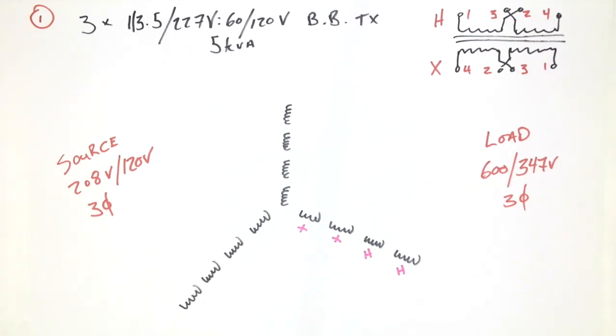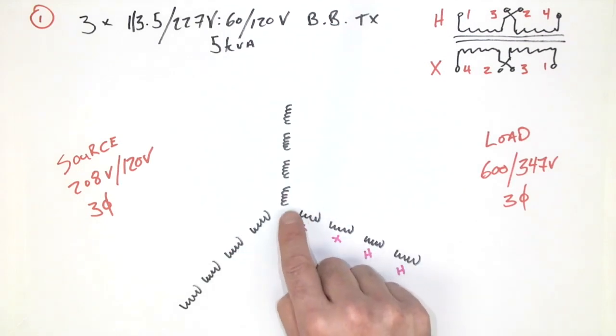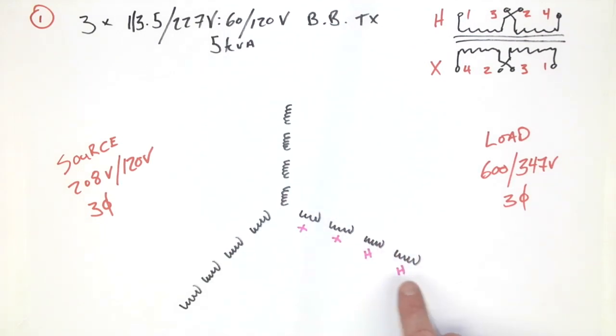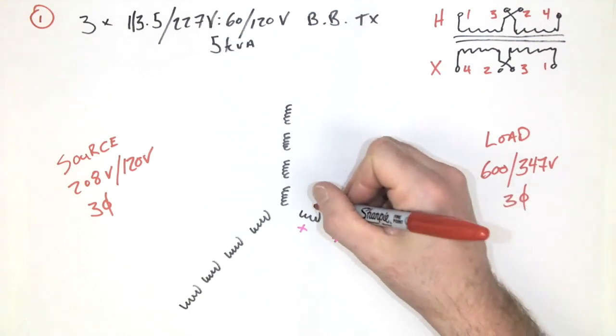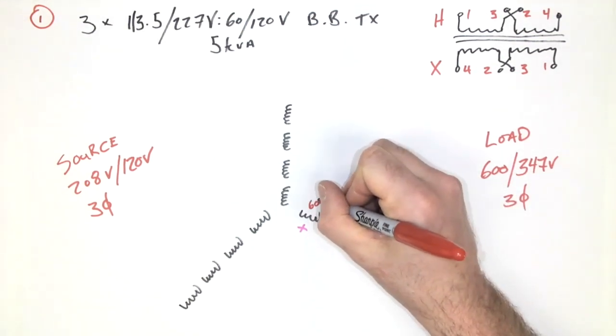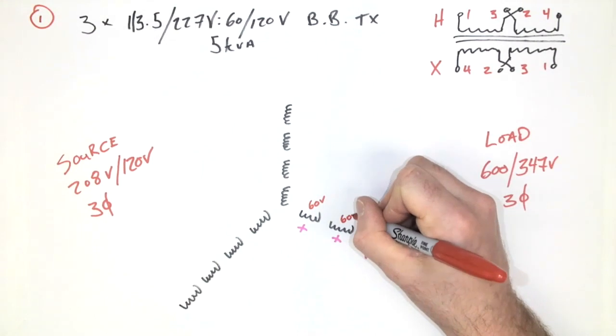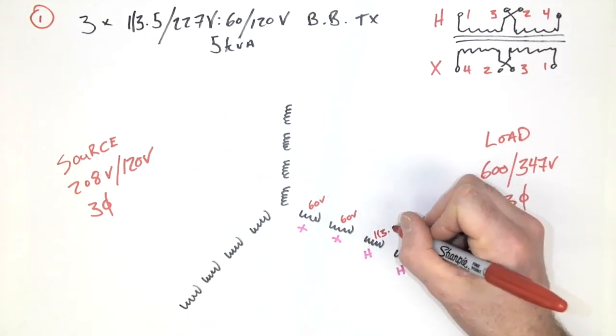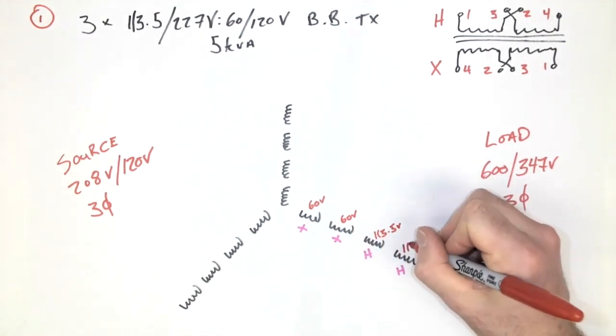Now, there is no standard for when the X windings have to be at the star point or when they have to be out here at the outer reaches of the star configuration. It's something that you will see as you're building the circuit where it is necessary to make that star connection. So first off, I'm just going to write in here the voltages of my X windings. Those are the low voltage, and the voltage ratings for my H winding, which are the high voltage.